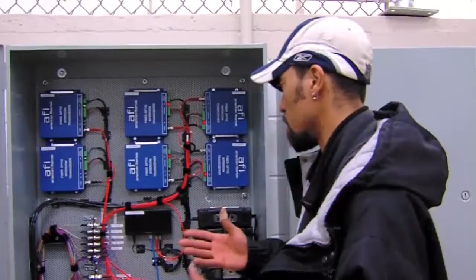On copper, the intercoms come back to these fiber modules. The fiber modules turn the audio into light, which is then transmitted back into the building. None of the functionality of the system changed, nothing changed, we just added onto it. So you've got 4 extra doors, 2 of them alarm only, and 6 more intercoms. These intercoms are all fed off of here.